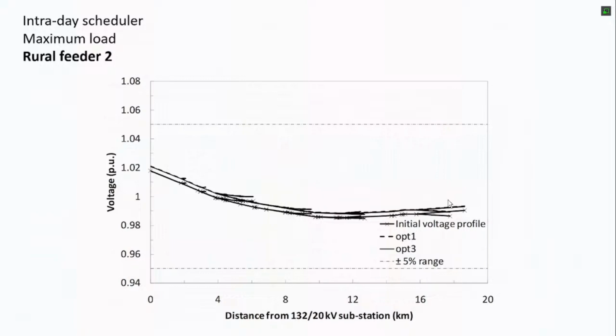In this case, the voltage was dropping slightly, and the optimization can increase it a little. This is interesting because both rural feeder 1 and rural feeder 2 are fed by the same transformer, so using just the transformer, we have two different feeders with different behavior: one has overvoltage, the other has decreased voltage. If we act only on the voltage at the beginning, it is difficult to combine both, so it is important to control the distributed energy resources of the generators connected along the feeders to stabilize things.